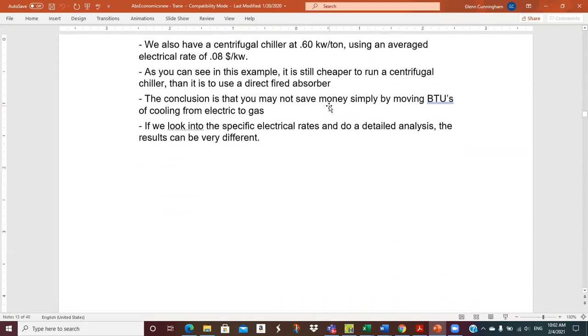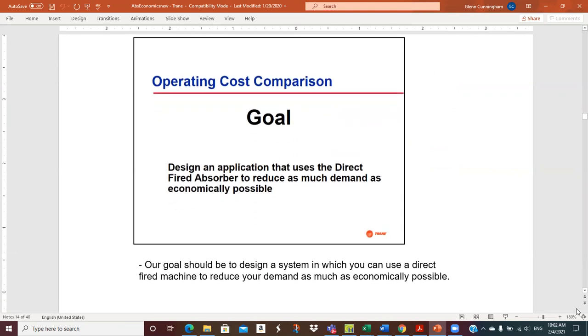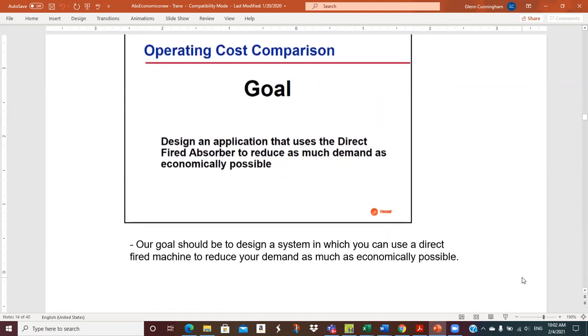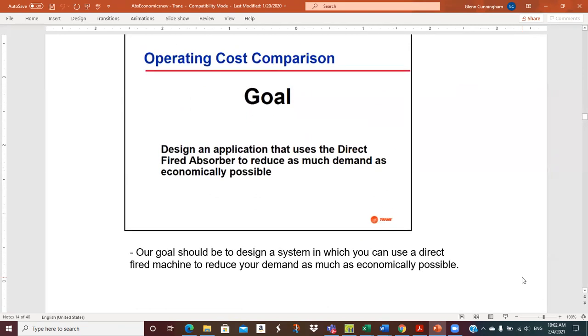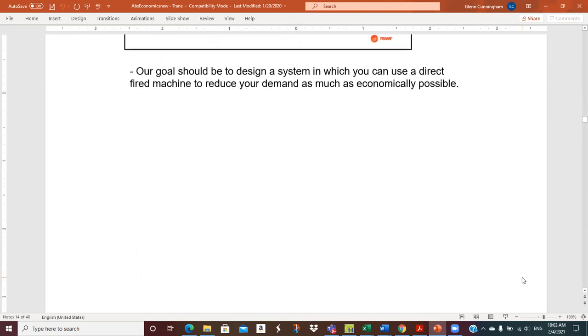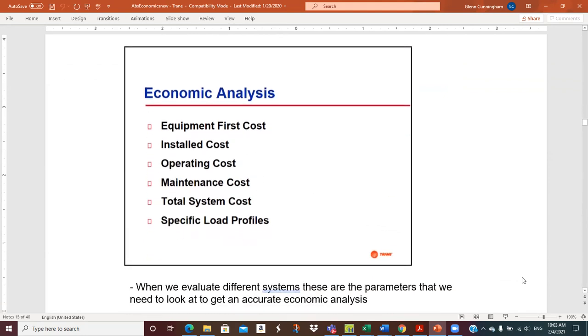So what we're going to do now is develop, this is the goal, probably some engineer's first assignment, to design an application that uses a direct fired absorption chiller to reduce as much demand as economically possible. This is going to look at a particular rate structure with on peak and off peak, where on peak energy is when in the summertime the cooling load would be the highest, which is when the chillers would be operating, and the chiller is probably the largest electrical load in the building. We're going to see if we can come up with a scenario that makes these absorption chillers look financially attractive, and this is a real situation that occurs.